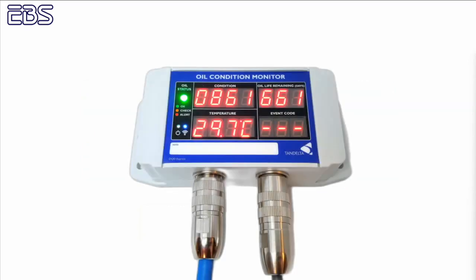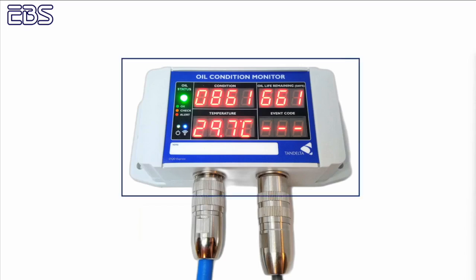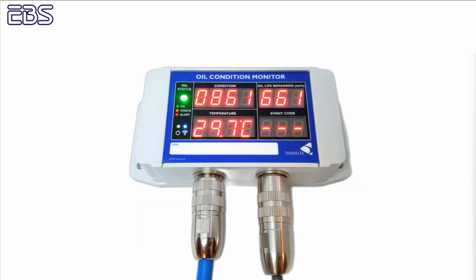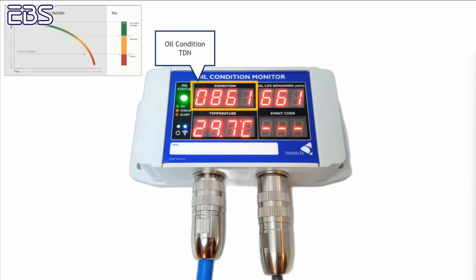Now we'll take a look at the data displayed on the TANDelta Sense2 kit. The Sense2 is designed for a standalone installation on any equipment. It's rugged and has an easy to read display, even in direct sunlight. In the top left-hand corner of the display, you can see the TDN displayed. This value shows you the overall condition of the oil for your equipment. The TDN limits change based on your application, and these limits can be found on our website and in our documentation.